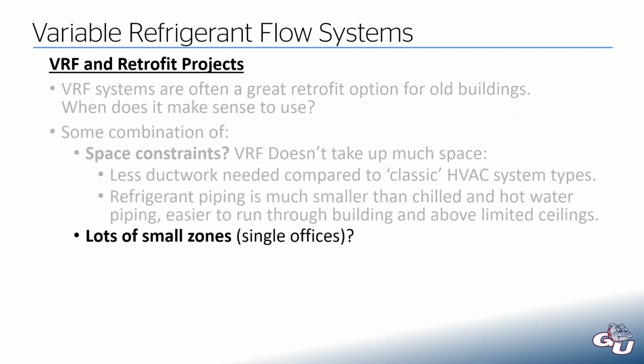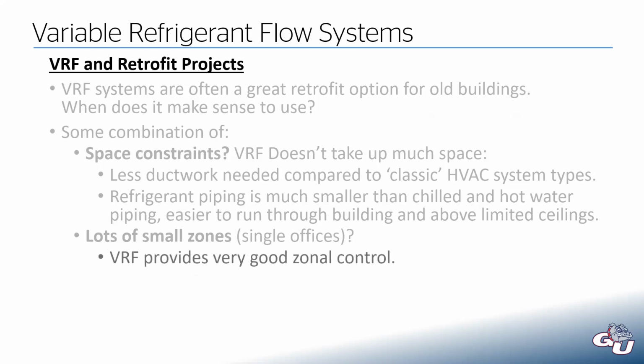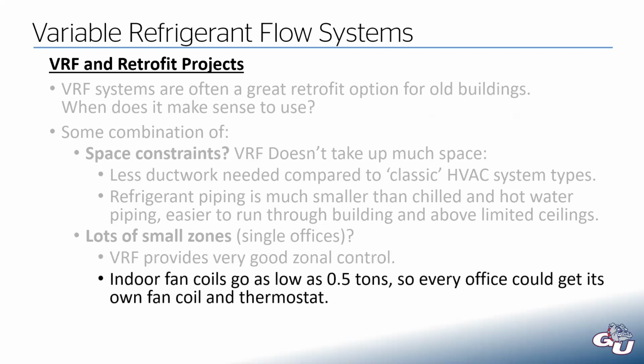If you have lots of small zones, like a bank of single offices, and everyone wants their own thermostat because that's the only way to make everybody happy, VRF will provide extremely good zonal control. Those indoor units go as low as 0.5 tons, which is a very, very small unit. Extremely small. That's as small as you can really get. And so every single office in that building could get its own little half-ton indoor fan coil and their own dedicated thermostat.